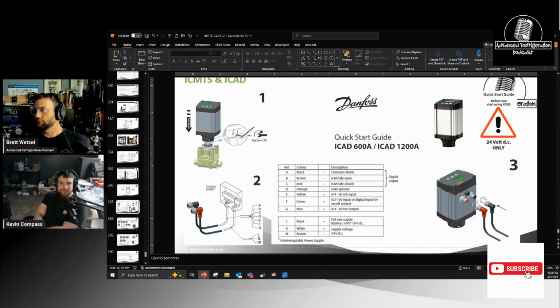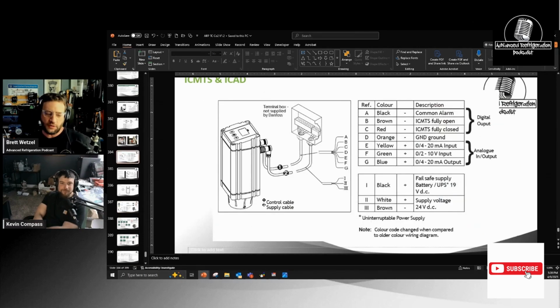Anywho, so continue. Okay, so make sure you've got 24 volts DC at it and it's not shorting out. And make sure that if it has a battery backup, it's good.